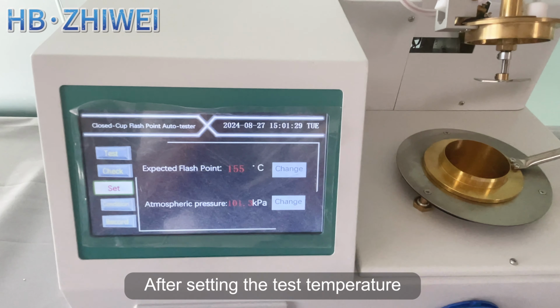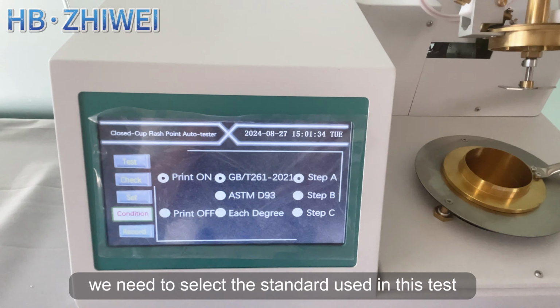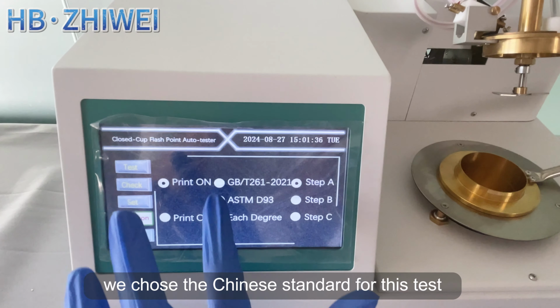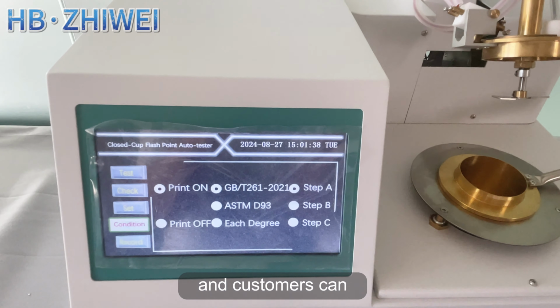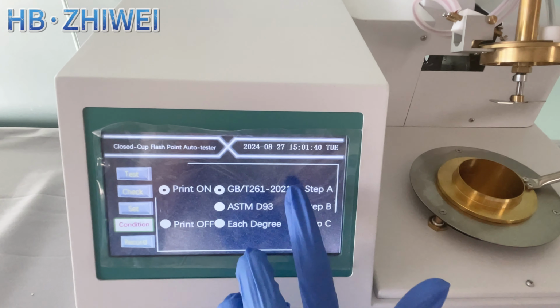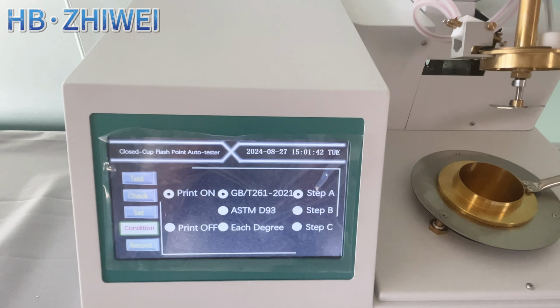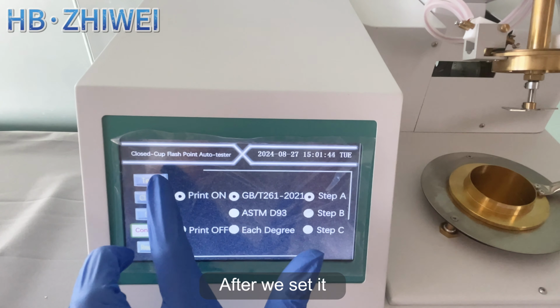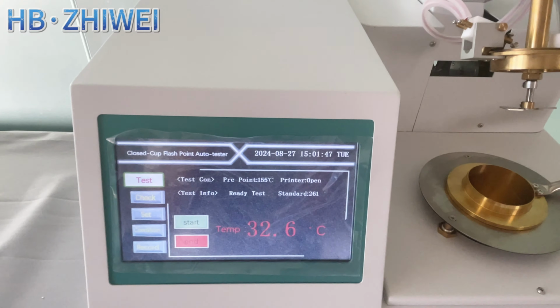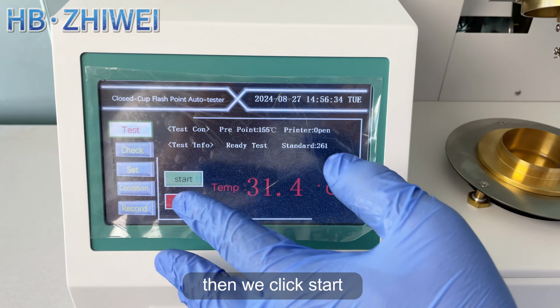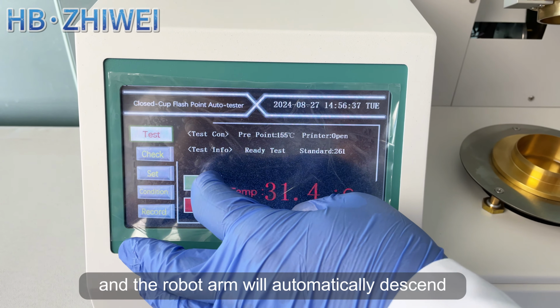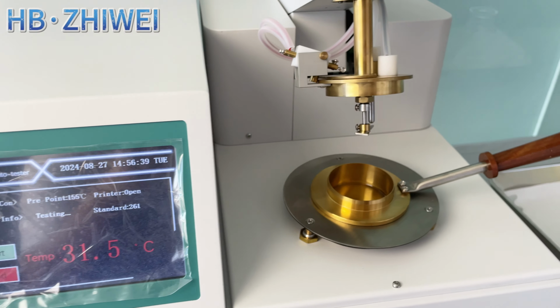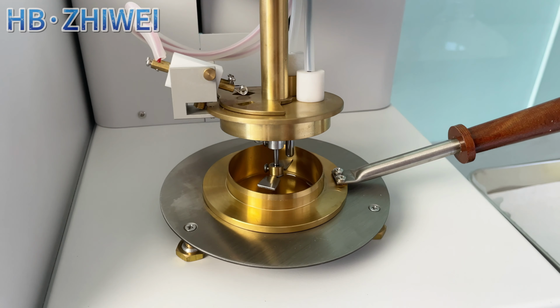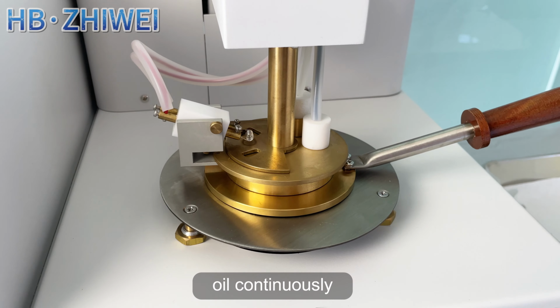After setting the test temperature, we need to select the standard used in this test. We chose the Chinese standard for this test, and customers can choose the standard according to their needs. After we set it, click Test. Then we click Start, and the robot arm will automatically descend. The stirring paddle will start to stir the oil continuously.